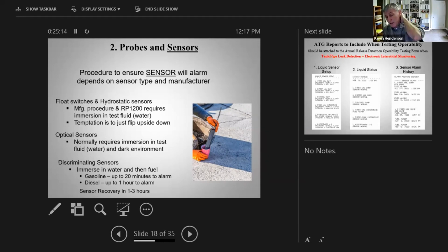And with a discriminating sensor, I really do not like to deal with these. I've only got one place that has these, and they're just kind of a pain in the butt, honestly. But what you would do is, of course, immerse it in water, hit the alarm, then immerse it in fuel, whatever fuel is in the tank, and verify that it will go into alarm with that. So the typical Veeder-Root sensor, in a gasoline environment, can take up to 20 minutes to go into alarm. And if it's diesel fuel, it can take up to 1 hour for it to go into alarm. So it's not a lot of fun testing those, but you do what you got to do, of course, and then it takes 1 to 3 hours for those discriminating sensors to recover. They got to dry out completely before they'll go out of alarm. I'm happy we don't see many of those around.